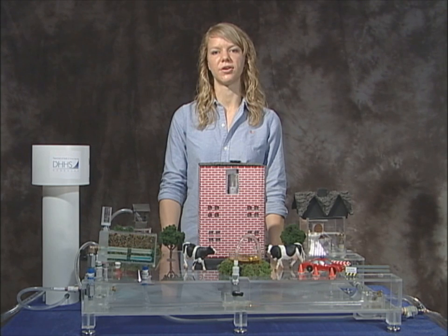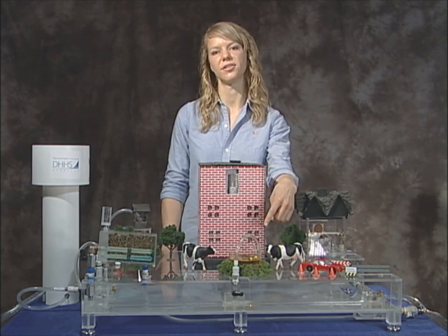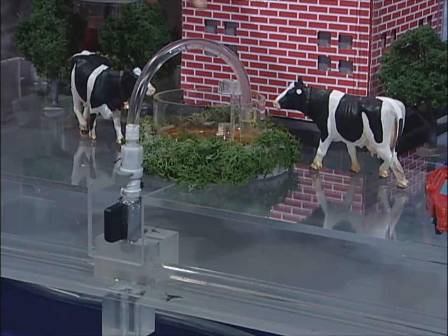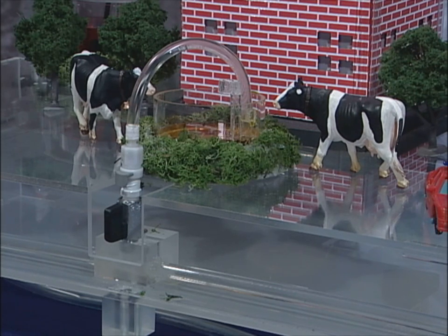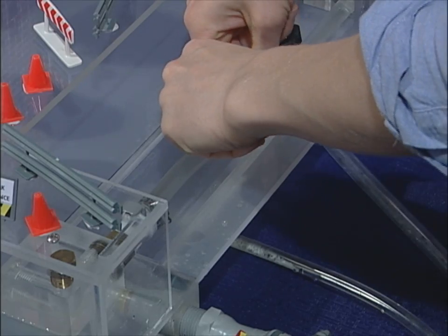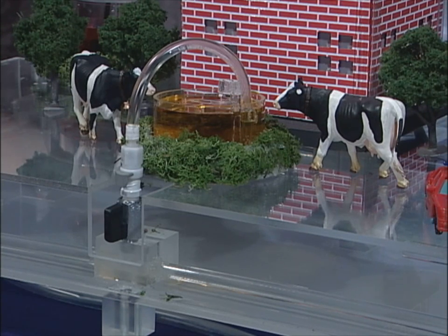The third backflow scenario demonstrates a back siphon event. This scenario is a submerged inlet in an elevated stock tank. You can see positive pressure under normal conditions where the stock tank is filling as water flows from the public system into the tank. If, however, an episode requiring large water demand somewhere else in the system, especially upstream, takes place, such as a large fire that requires large flow of water or a potential line break requiring repair, the pressure in the system can drop to a degree where there is a reversal of flow and water siphons into the system from the connected stock tank.